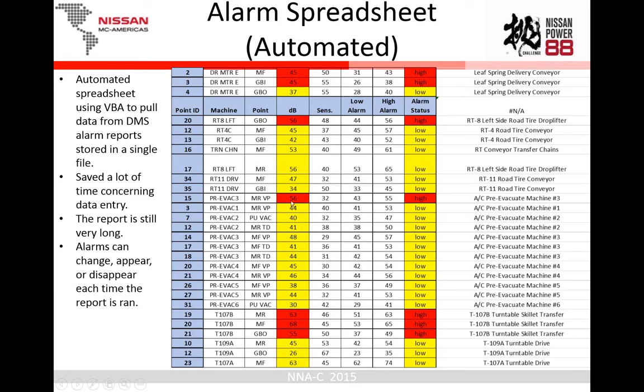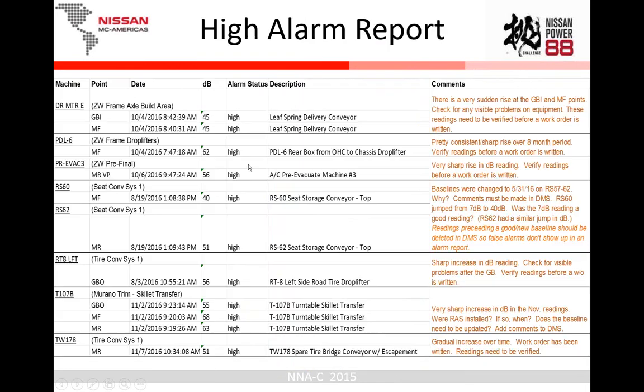Like this pre-evac vacuum pump right there—it could be a high alarm this month, and then three months from now when you run it again, it could be gone, and you don't know why. So you have to go investigate and find out why. They may have replaced that part, or if I wrote a work order on it, then they definitely replaced it, which might very well be the reason it dropped out of alarm.